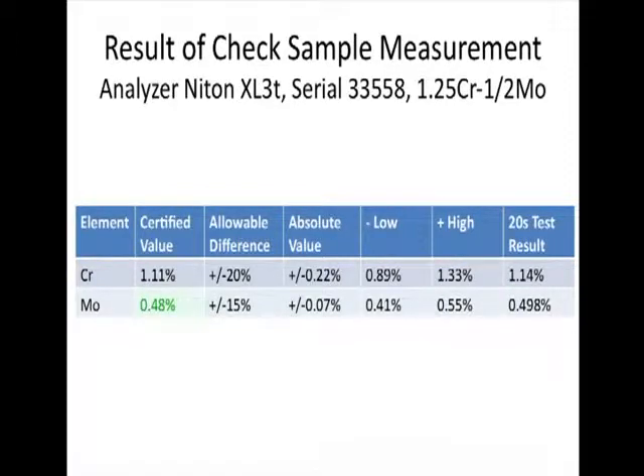The moly is certified at 0.48%, which multiplied by 0.15 for the plus or minus 15% allowable tolerance gives us an allowable deviation value of plus or minus 0.07%, establishing the acceptance range for moly from 0.41% to 0.55%, lower and upper limits. Our reading of 0.498% falls within this range. However, we will perform a detector calibration in any case, as it is simply good practice to do so on a daily basis. I'm going to take you through the detector calibration now.